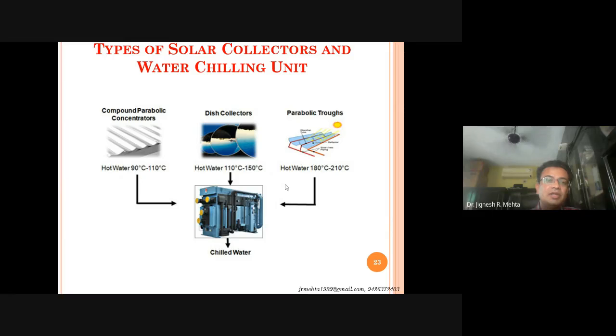And compound parabolic concentrator, CPC. The range of temperatures normally available with these collectors have been shown. Normally, as you try to get higher and higher temperature, the initial cost of the system increases, and many times the tracking related issues and maintenance cost also increase. So just out of fancy, one should not use the concentrating collectors. Dish collectors, hot water, 110 to 150, and for even higher temperatures, 180 to 210.